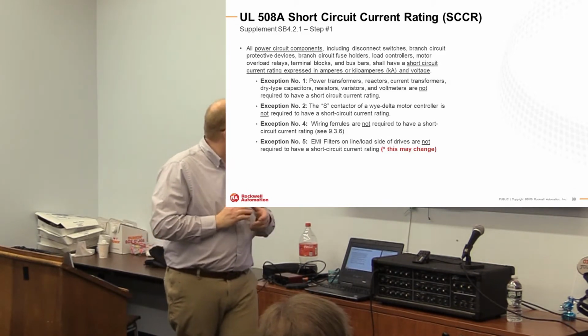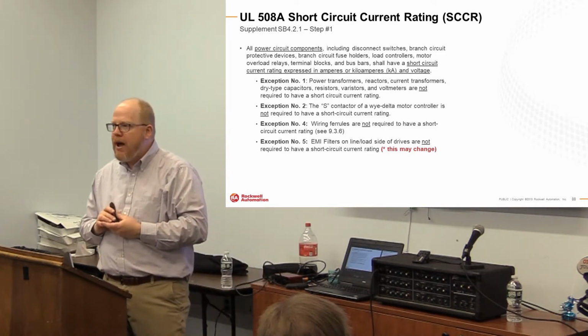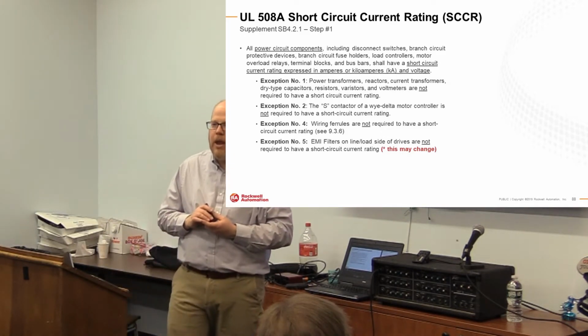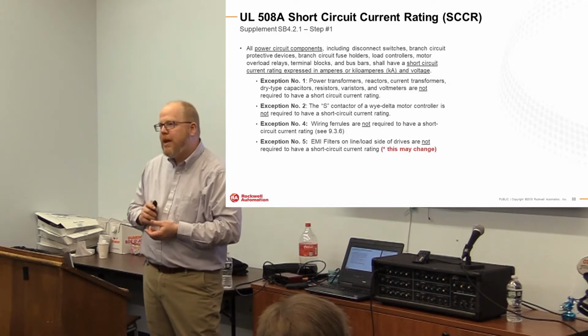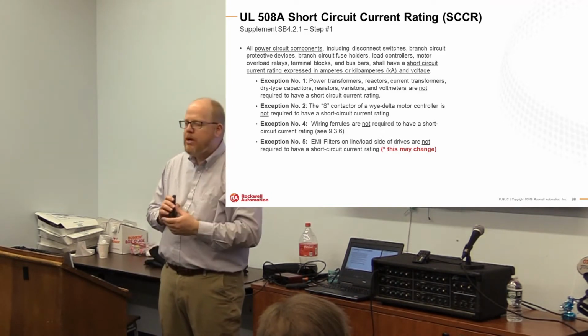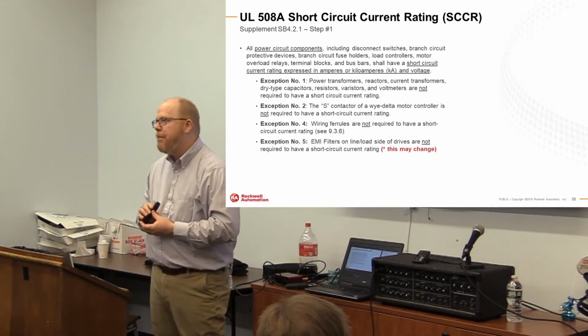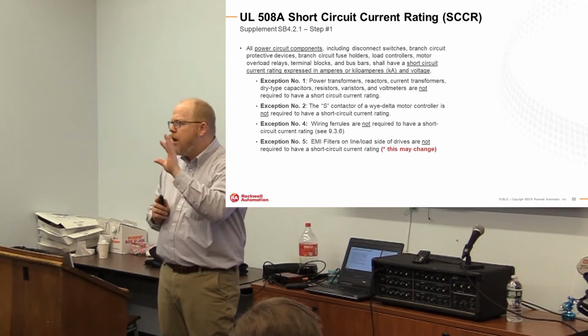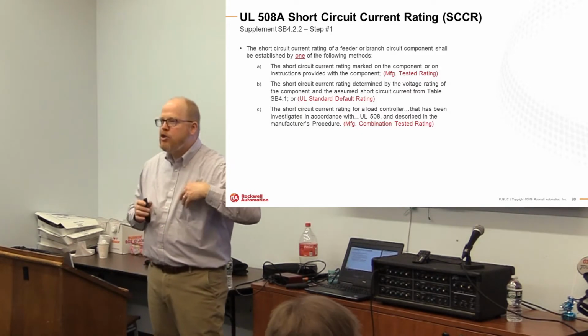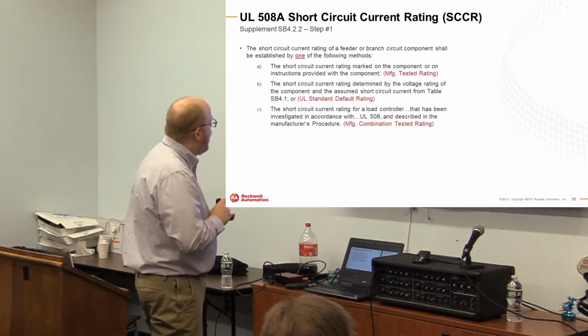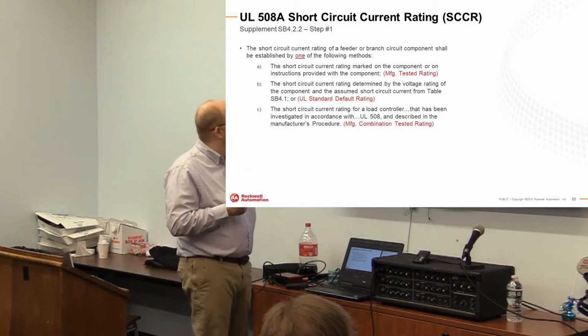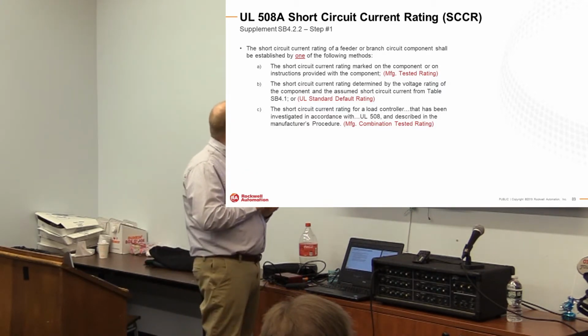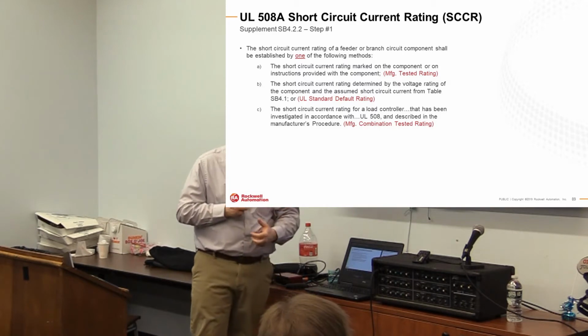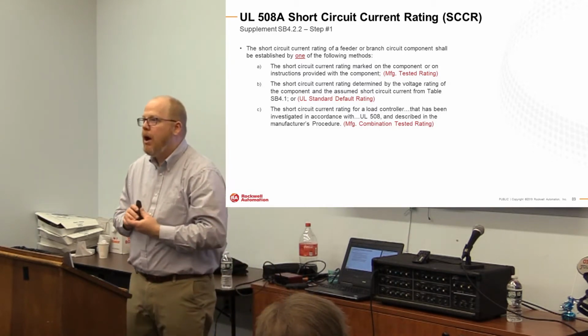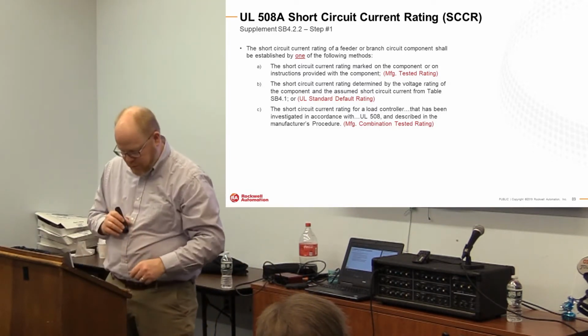The other exception that I want to clear up here is exception number 5 under EMI filters. That one is still in the air. They're still debating that one. That's why in the previous section, when I showed you things that are not being implemented yet, that's up in the air. So let's just talk about step 1. All right, so the short circuit current rating of a feeder or branch component shall be established by one of the methods. So we're talking here of a component.